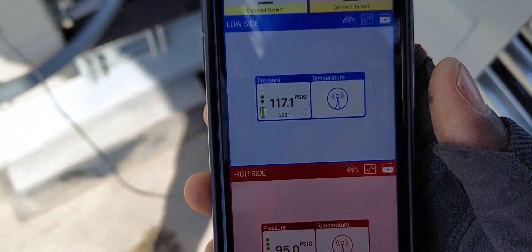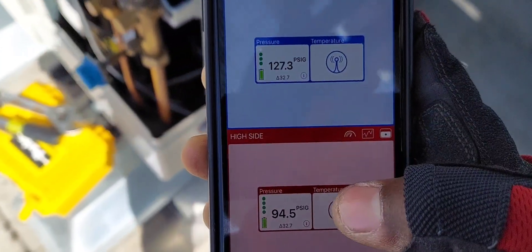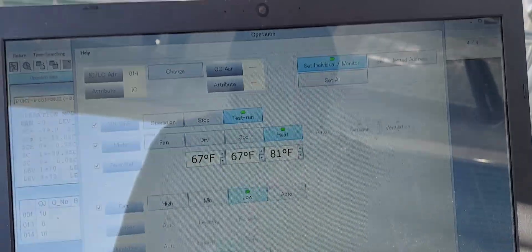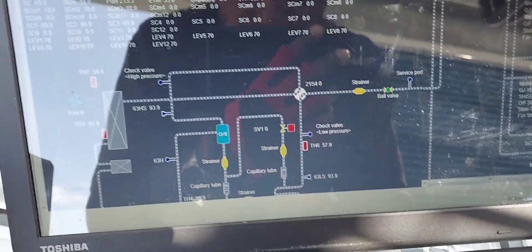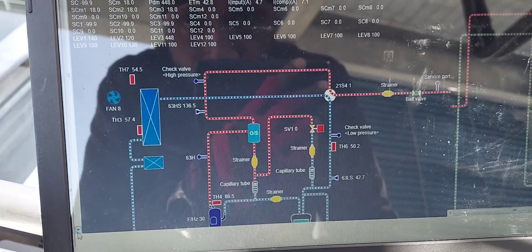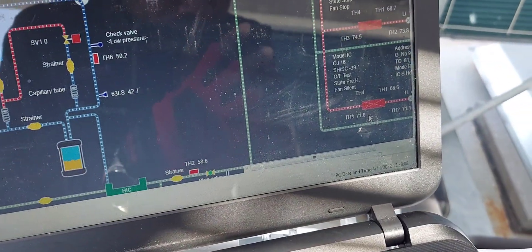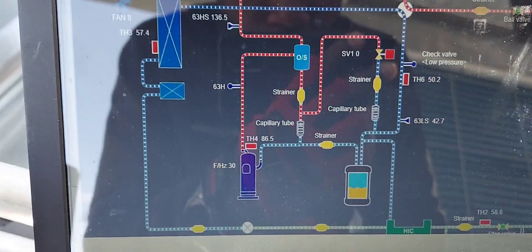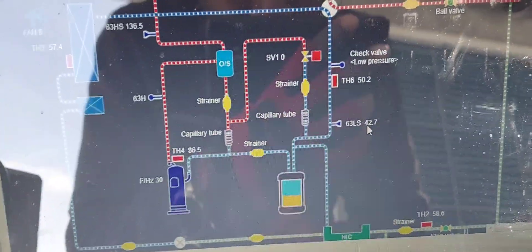Because we're running in heat mode, the suction is actually the high side and the high side is the low side. Let's look at the system in real time. I'll go to the piping diagram because that's pretty cool. Everything is alive right now — I have one indoor unit on. See what's going on: 42 PSI low side.